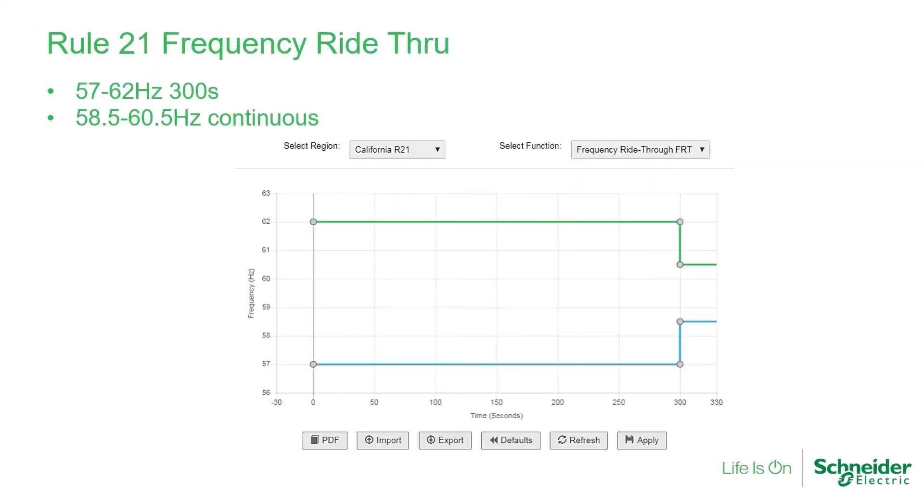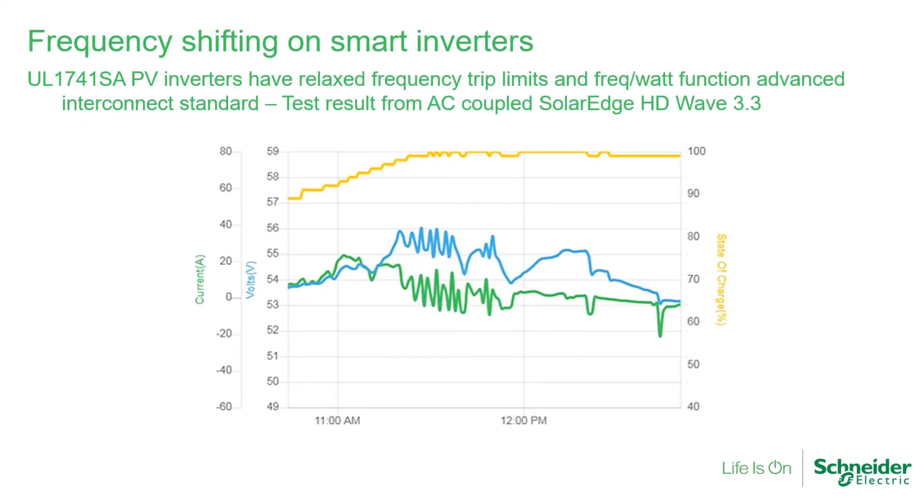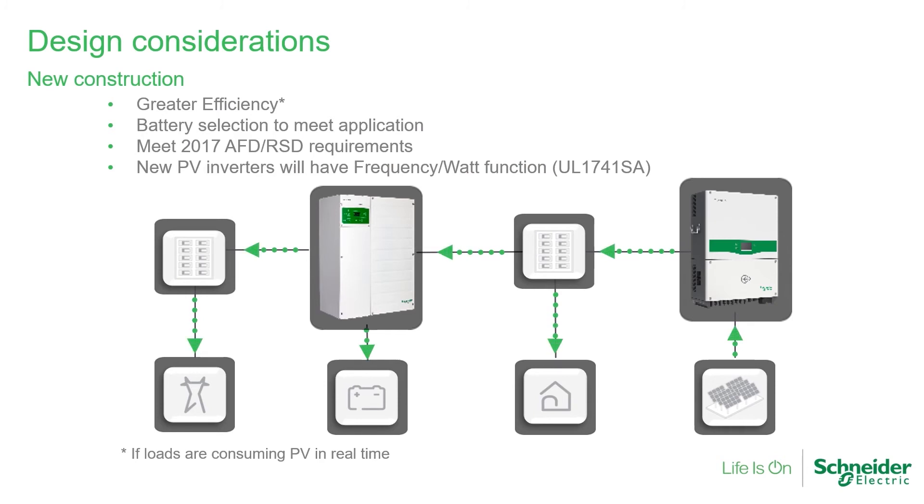Rule 21 compliant PV inverters will continue to operate for 300 seconds between 57 and 62 Hz. The Rule 21 frequency-watts function is optional; the default slope is indicated. Smart PV inverters have a more relaxed frequency window and trip time. The frequency-watt function will allow the PV inverter to ramp down output power rather than completely shut it down. Most grid-tie PV inverters are greater than 96% efficient, so this can improve overall system efficiency if loads are consuming PV energy in real time. In regions without time-of-use, lead-acid chemistry may be used in lieu of more expensive lithium technology as a standby battery, especially when utility outages are rare and of short duration. Microinverters already comply with 2017 arc fault rapid shutdown requirements, and string inverters will typically have arc fault protection and can easily meet rapid shutdown requirements when used with module level power electronics.